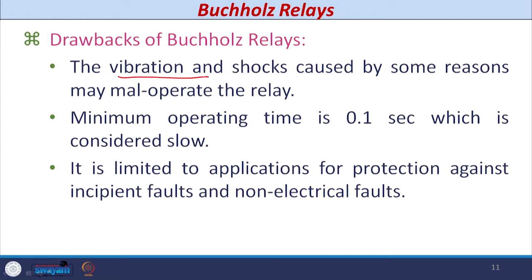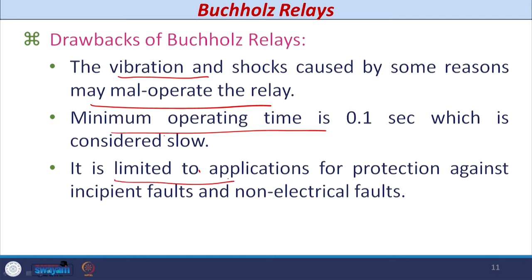Now let us see the drawbacks of the Buchholz relay. First, whenever vibrations or shocks occur — due to an earthquake or mechanical vibrations — such a relay may mal-operate, so we need some arrangement to avoid this. Second, the time of operation of the Buchholz relay is of the order of 0.1 second or 100 milliseconds, which is considered lower compared to other devices. Third, the application of the Buchholz relay is limited to protection against incipient faults or non-electrical faults; it cannot be used for protection against electrical or internal faults in the winding or core.